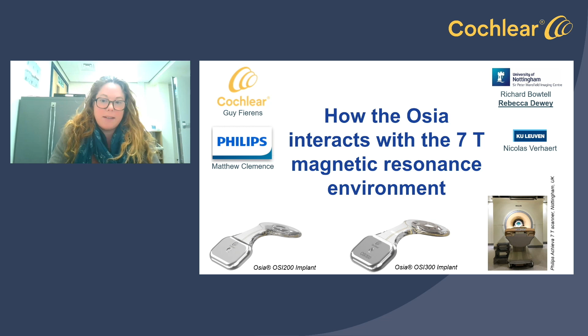New models of implanted auditory prostheses now pose very few safety concerns being MR scanned in field strengths up to and including 3 Tesla. So much so that we can now scan these individuals for research where there's no direct benefit to the participant of undergoing imaging. However, at 7 Tesla, it's a different story. Having previously been a research-only field strength for MR, it's now being approved by the FDA for patient scanning, and we're expecting in the USA at least that patients and members of the public are going to be given the opportunity to have diagnostic medical imaging at this field strength at some point in the future.